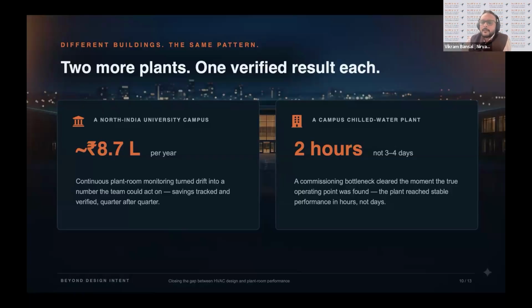And for one of the campuses, there was a call during commissioning: the chiller was not becoming operational. It was assumed that the pump was not performing, not able to give the required flow. But when we ran through the data, the pump was showing the flow and head that was being delivered at site. So we learned the pump was running at a higher head than the design intent.